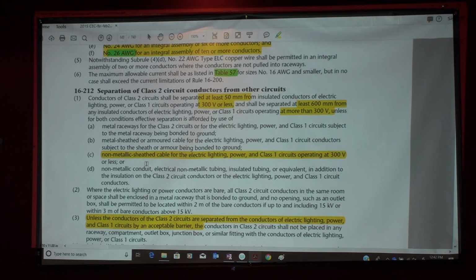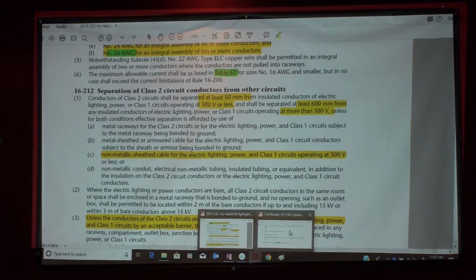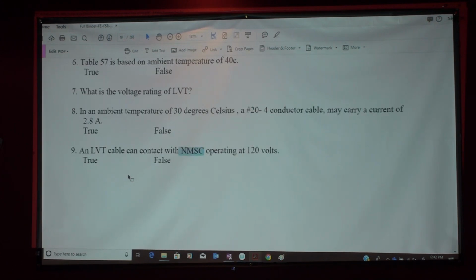So what does it mean by come in contact? They're just running beside each other. Did I say that they are intertwined in any way? No. What I said is they're just placed next to each other. Can come in contact with the non-metallic sheathed cable means you don't need a barrier. That's what my question says. Well, it is non-metallic sheathed cable, so technically it's not conducting in any way. So I believe it's right. And up to 120 volts, absolutely. If I had given you a 600 volt circuit, then the answer would be no. Yeah, I agree. My answer is right.